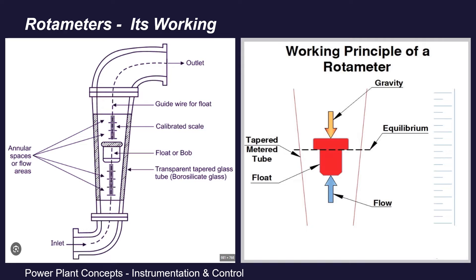— that is the drag force, the float rises up. The float is attached to a vertical guide wire to move up and down along a fixed vertical axis only. As the float is placed in a tapered tube, the upward movement of the float creates an annular space between the float and the walls of the tube. The larger the amount of fluid flow, the higher the float is raised, and thus more will be the annular area to allow passage of flow between the float and the tapered wall.